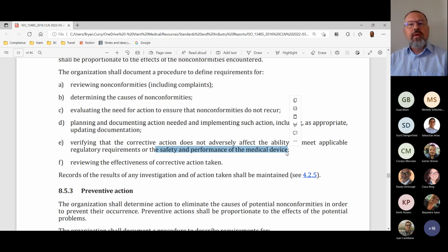You also want to evaluate whether or not the corrective actions that you've implemented might inadvertently generate a new failure mode that you had never seen before, because you've changed something in the manufacturing process, and suddenly your manufacturing process has all of these new failure modes that are not currently captured by your risk management program.